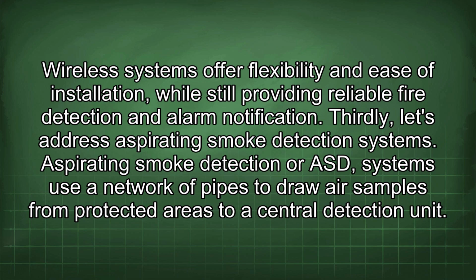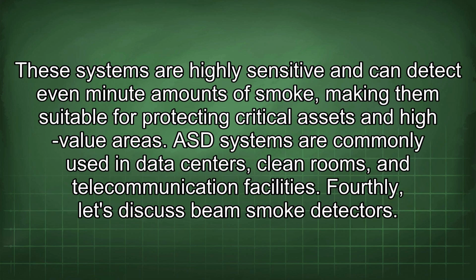Thirdly, let's address aspirating smoke detection systems. Aspirating smoke detection, or ASD, systems use a network of pipes to draw air samples from protected areas to a central detection unit. These systems are highly sensitive and can detect even minute amounts of smoke, making them suitable for protecting critical assets and high-value areas. ASD systems are commonly used in data centers, clean rooms, and telecommunication facilities.